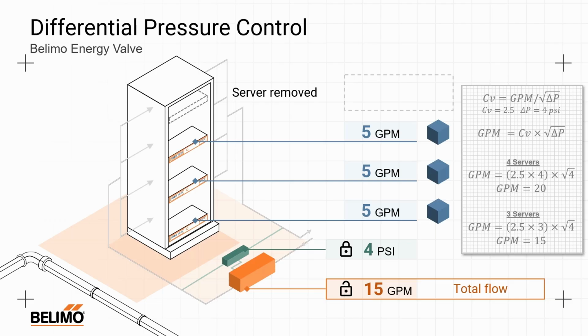So I either just had a light bulb go off in your head or bored you to death with math you already understood. Either way, I appreciate you sitting through this with me. Differential pressure control is available in the Belimo energy valve natively, meaning if you apply a differential pressure sensor connected to the energy valve and tell it that you want to do differential pressure control, it'll ask you what your maximum flow rate is and what differential pressure you want to control to, and it will control on its own. That means it doesn't need a control signal to do this. It's maintaining that fixed differential pressure that you put in place. It is a Modbus and BACnet capable device, so you can monitor everything that's going on and have the ability to change the parameters at any time. But it gives you a lot of functionality and a lot of options in terms of how to control your product.